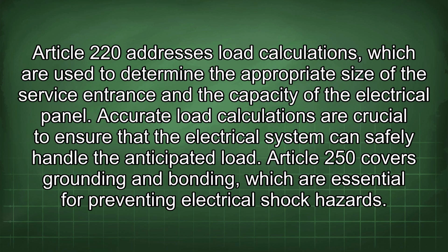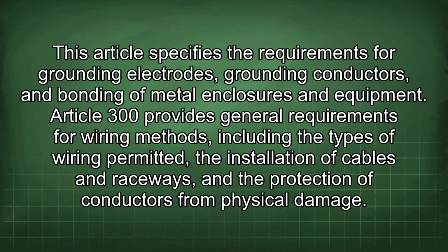Article 220 addresses load calculations, which are used to determine the appropriate size of the service entrance and the capacity of the electrical panel. Accurate load calculations are crucial to ensure that the electrical system can safely handle the anticipated load. Article 250 covers grounding and bonding, which are essential for preventing electrical shock hazards. This article specifies the requirements for grounding electrodes, grounding conductors, and bonding of metal enclosures and equipment.